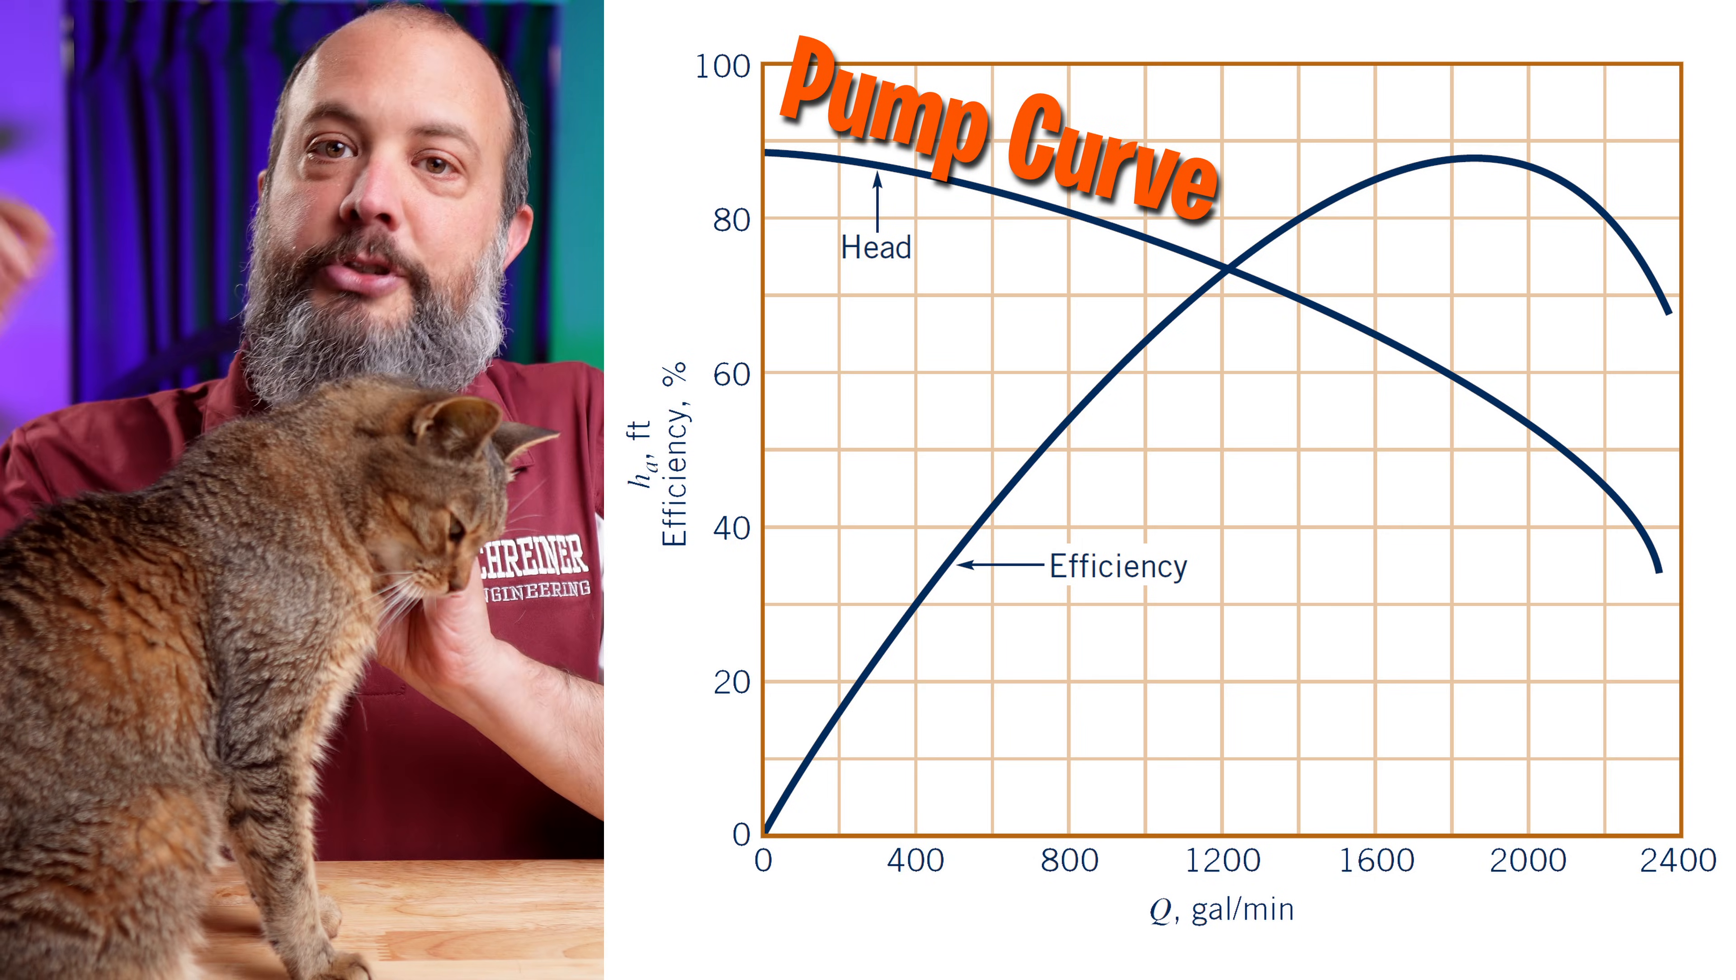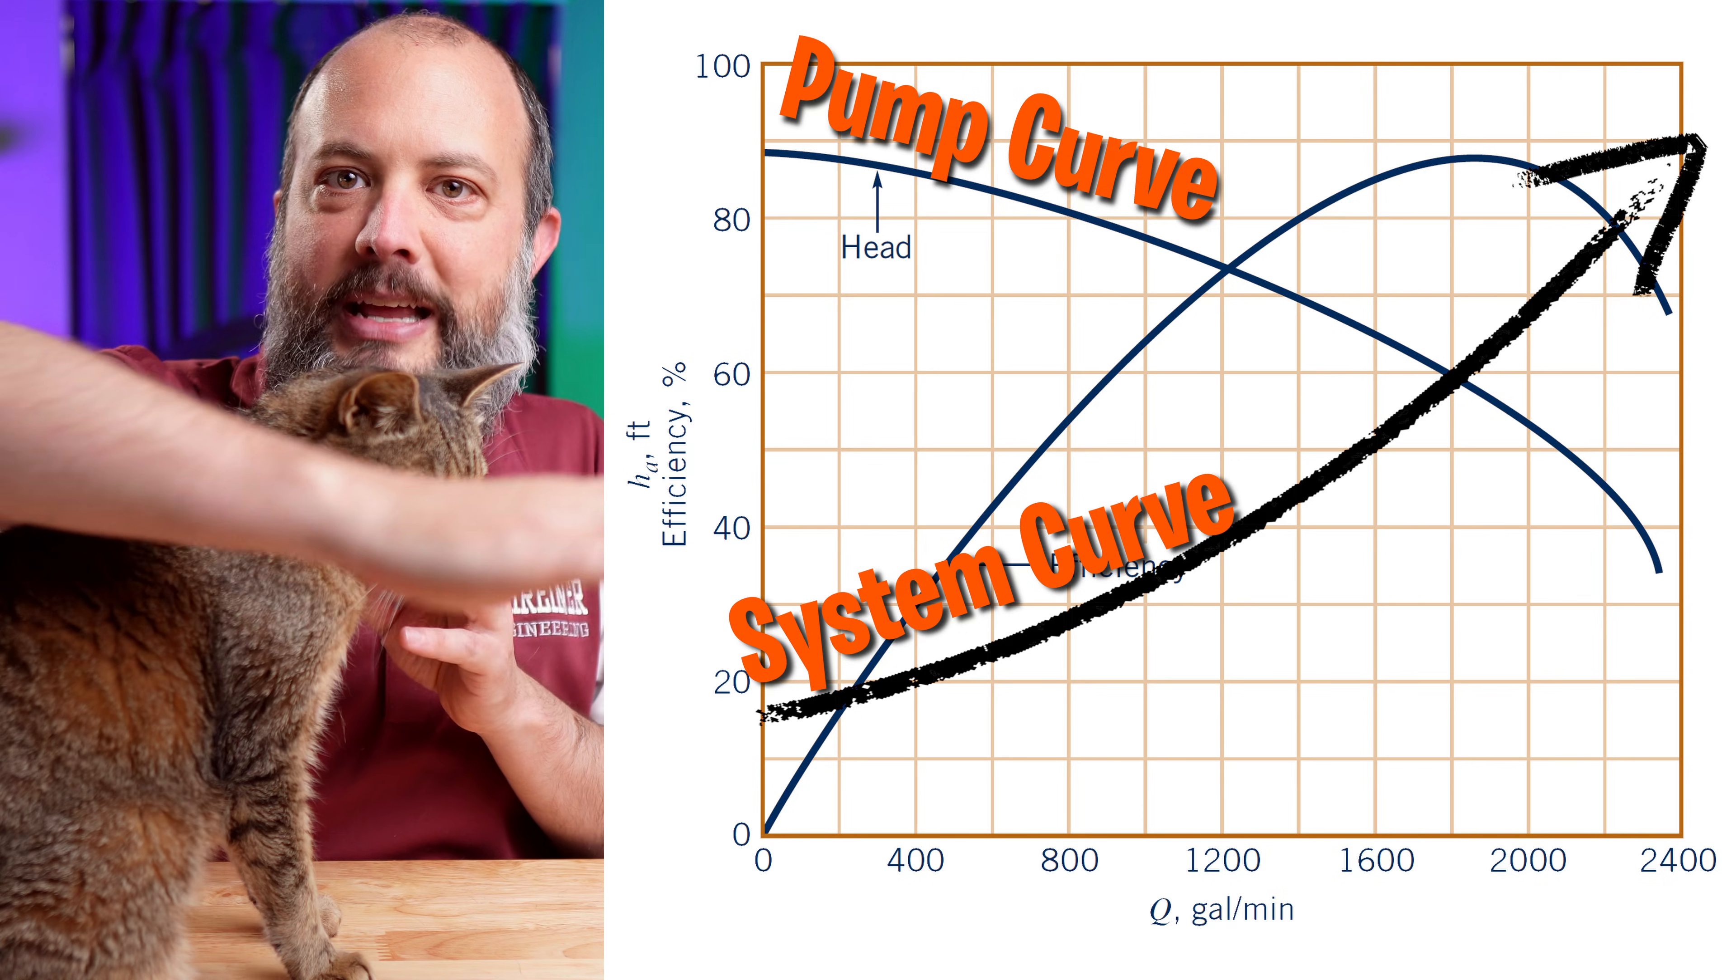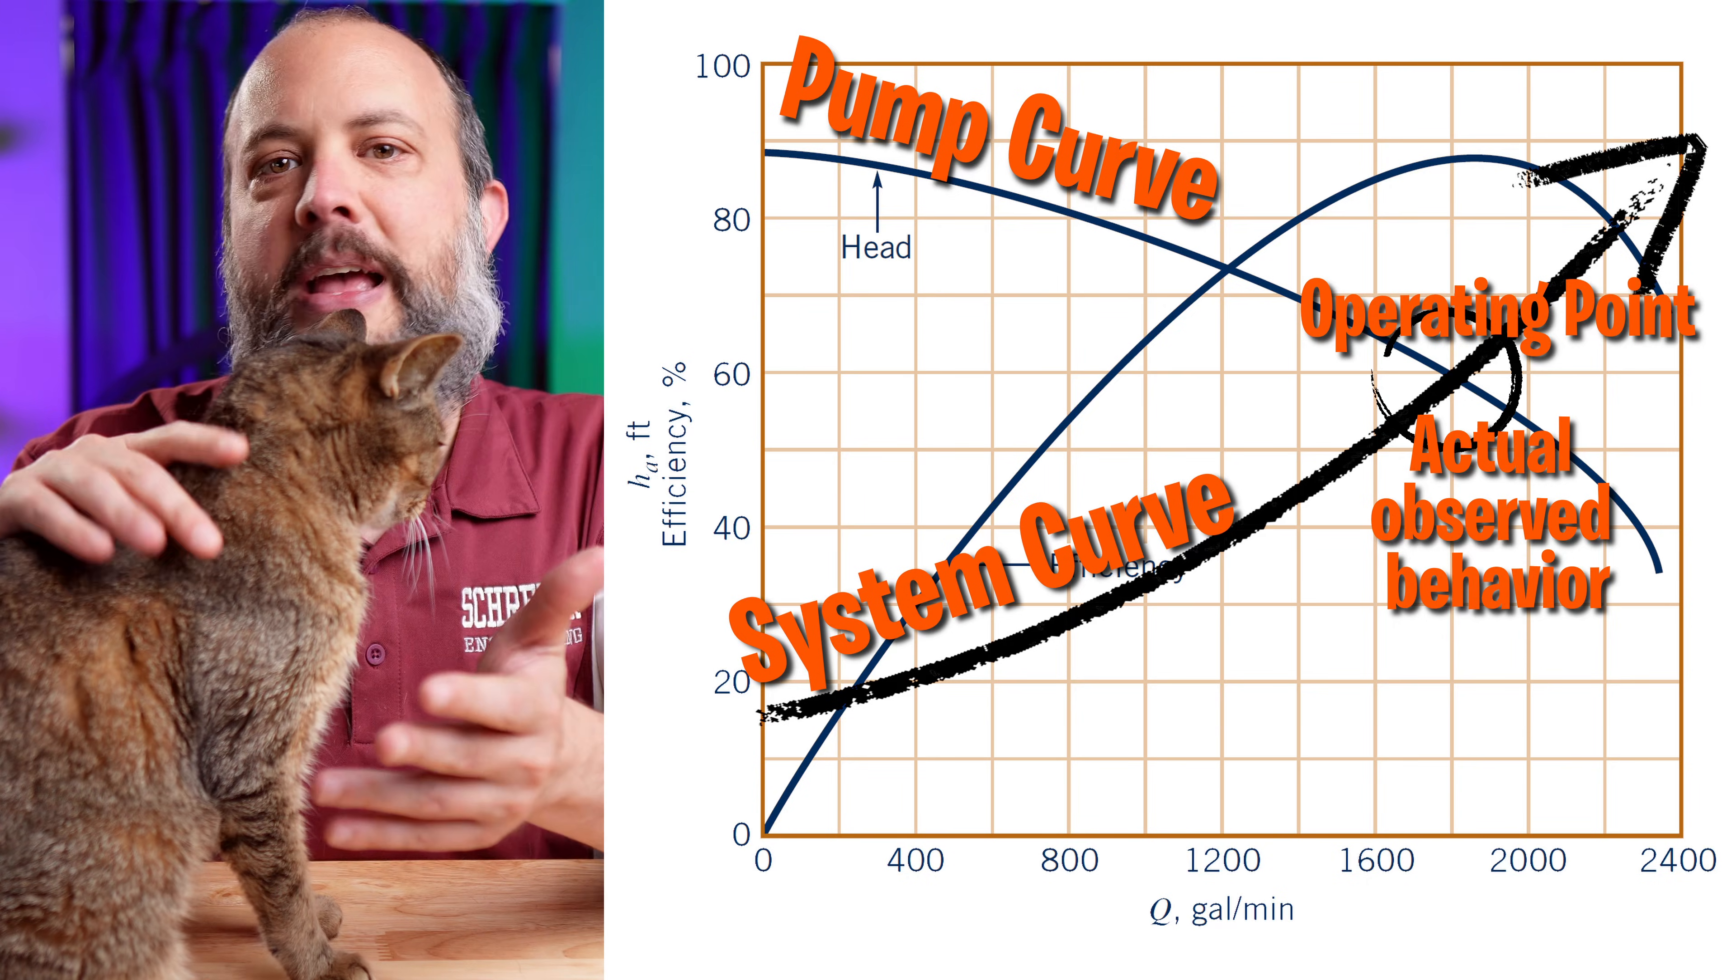So while a pump curve will start off high and then decrease, as more flow, less pressure, a system curve will start off low and increase. That is, as flow rate increases, the head loss increases. And so wherever those two curves meet, that is what your final actual system behavior will be.